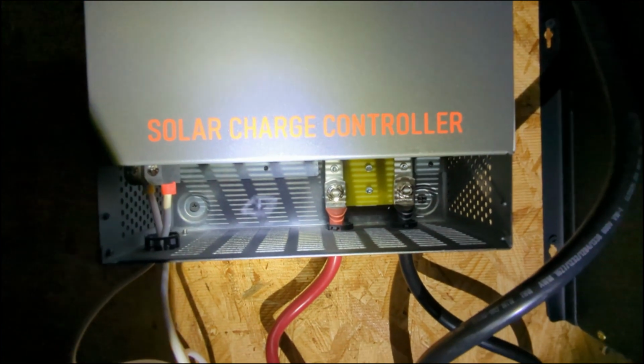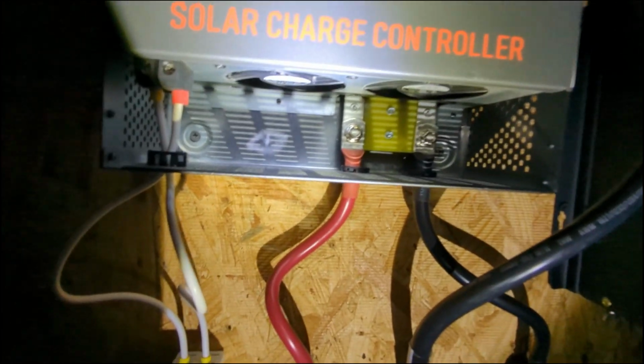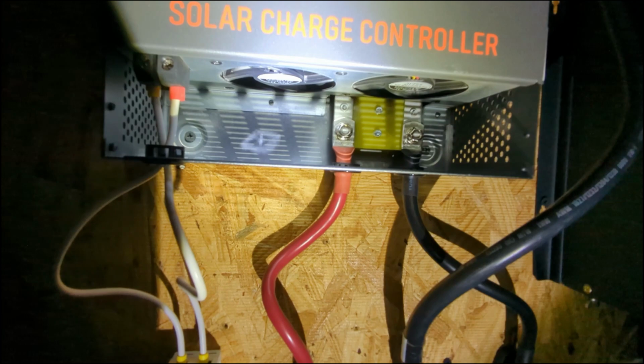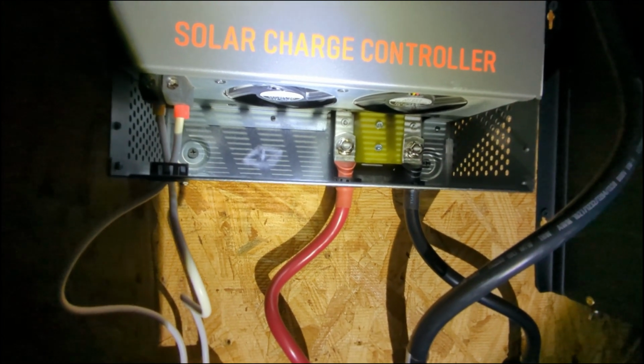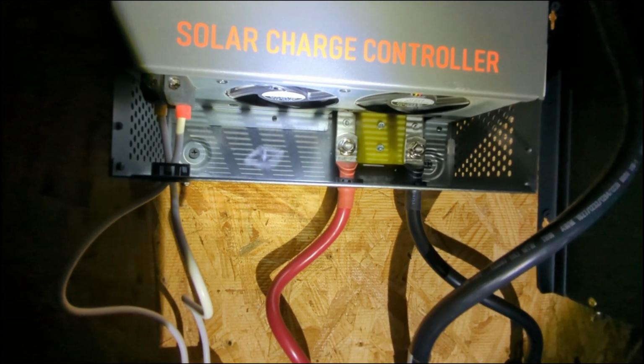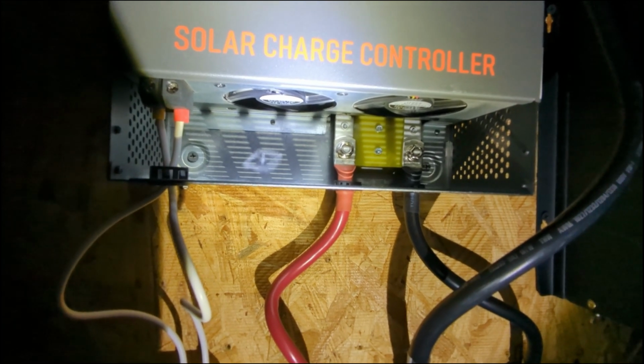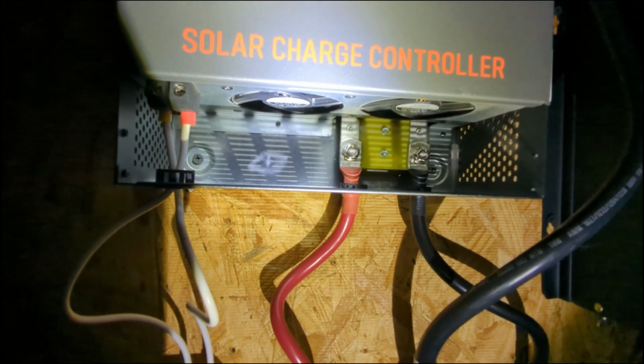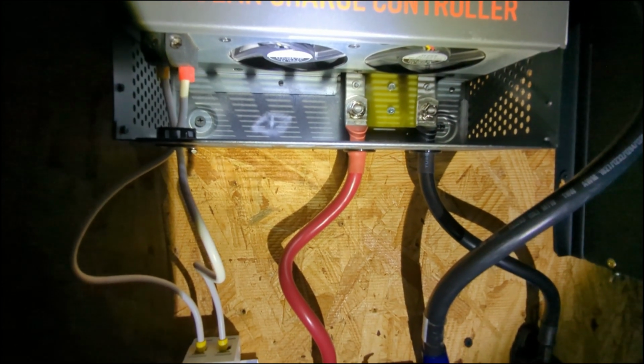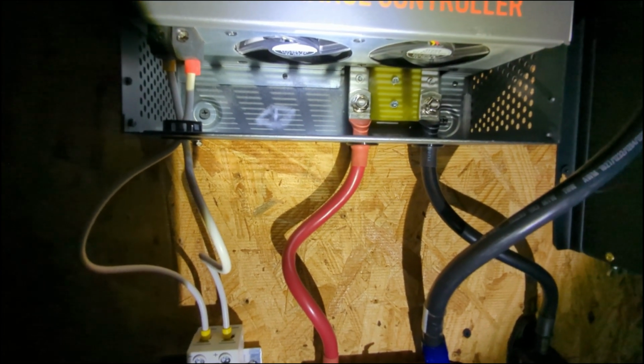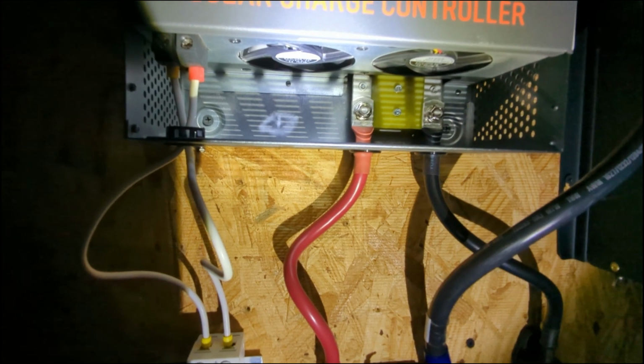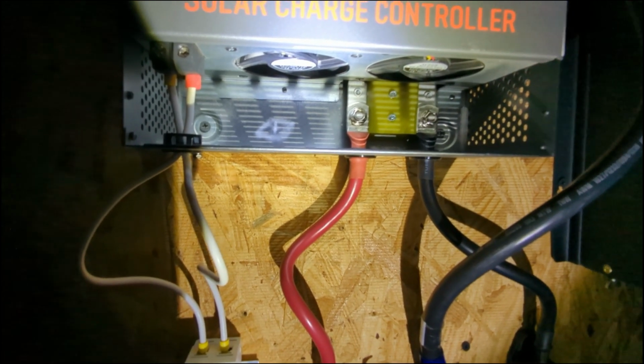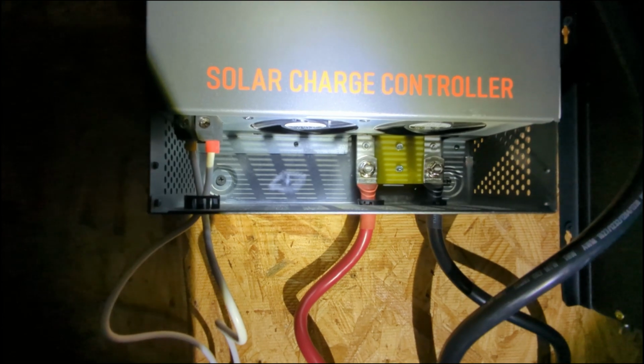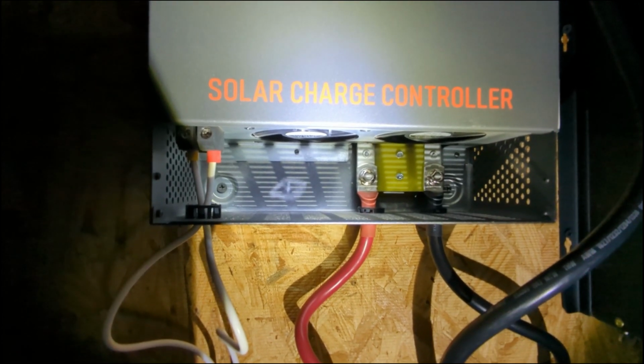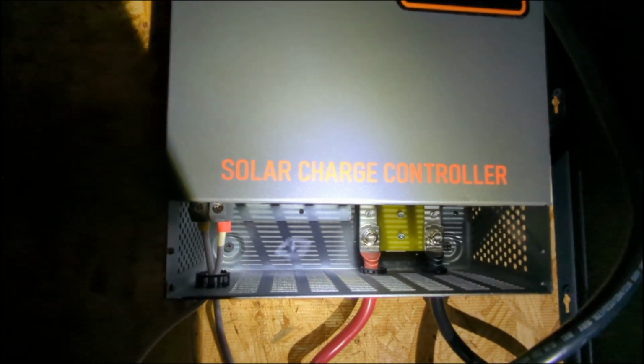On the right-hand side is your battery connections. I'm running 2-gauge wire, which is what the manual suggested to use. This unit supports up to 140 amp charging current. I feel like 2-gauge wire should be enough since I'm not pushing anywhere close to the maximum wattage this unit supports. I believe this unit supports up to 6,500 watts. So far, the highest I've seen with my system is about 4,000.